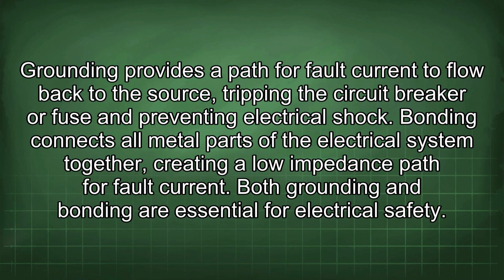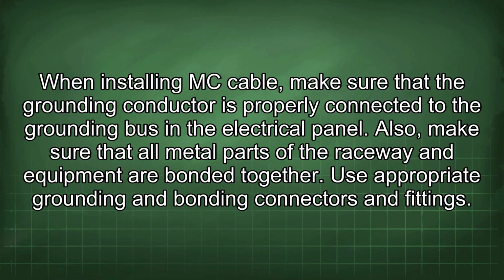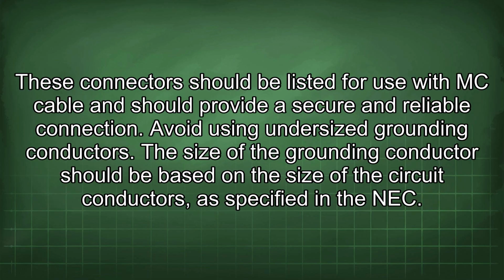preventing electrical shock. Bonding connects all metal parts of the electrical system together, creating a low impedance path for fault current. Both grounding and bonding are essential for electrical safety. When installing MC cable, make sure that the grounding conductor is properly connected to the grounding bus in the electrical panel. Also, make sure that all metal parts of the raceway and equipment are bonded together. Use appropriate grounding and bonding connectors and fittings. These connectors should be listed for use with MC cable and should provide a secure and reliable connection.